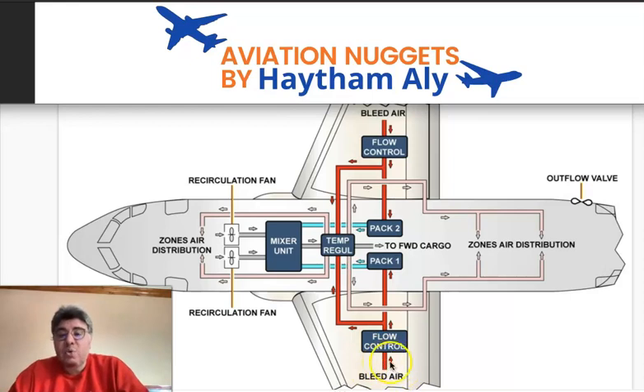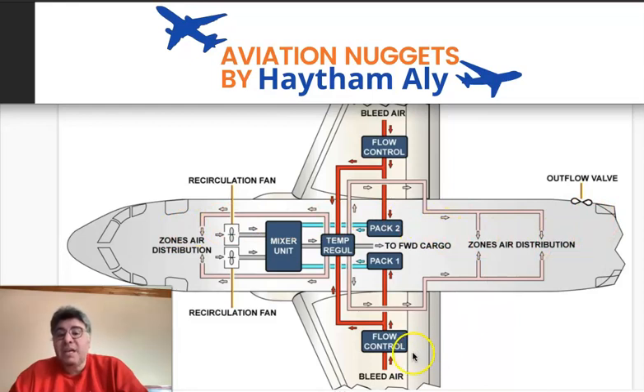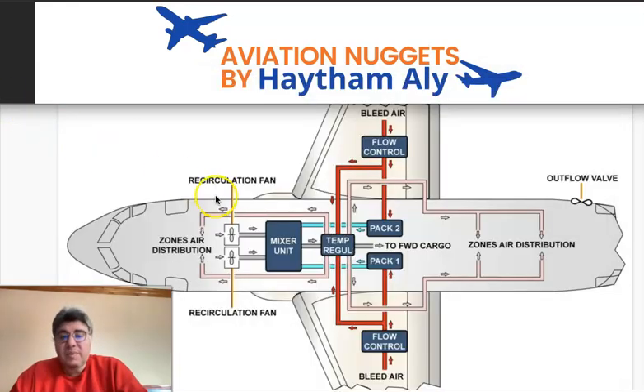We need the cabin and cockpit temperature to be within a comfortable range — like 18, 22, or 25 degrees Celsius. So the bleed air must be regulated from 150–200°C down to around 20–25°C. The air conditioning packs are responsible for this basic temperature regulation.